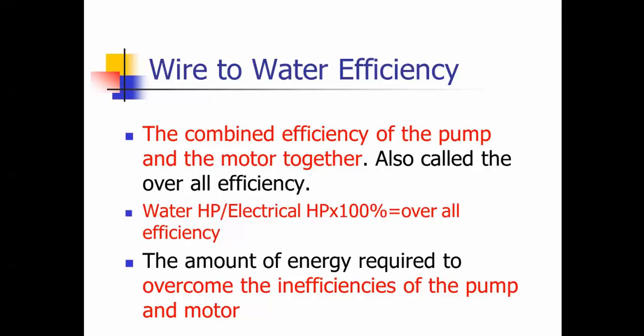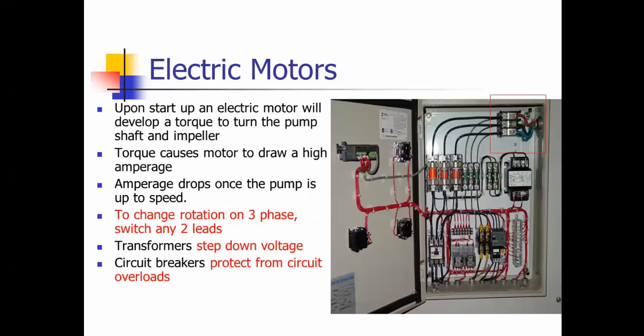Wire-to-water efficiency is the combined efficiency of the pump and the motor together. This is the formula, the second bullet. Wire-to-water efficiency is the amount of energy required to overcome the inefficiencies of the pump and motor. Electric motors: upon startup, an electric motor will develop torque to turn the pump shaft and the impeller, and that causes a draw of high amperage. Once the pump is up and running, the amperage drops once it's up to speed.